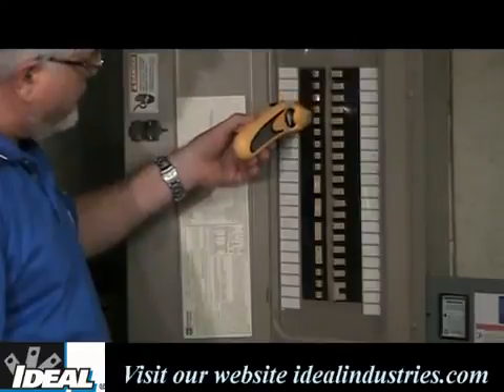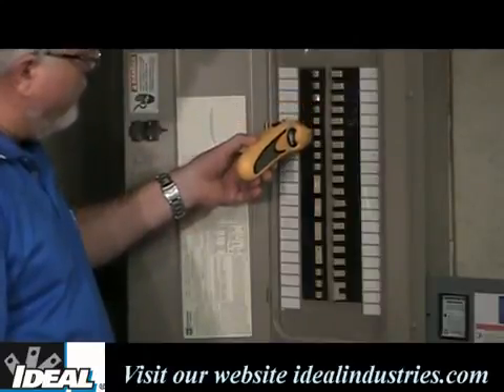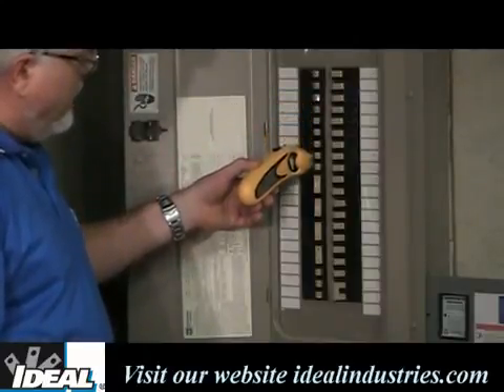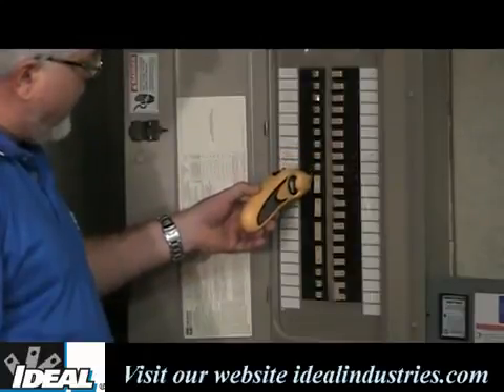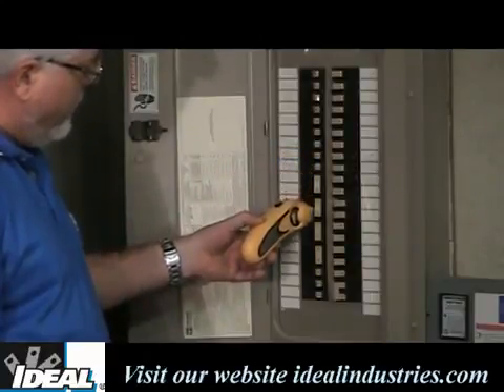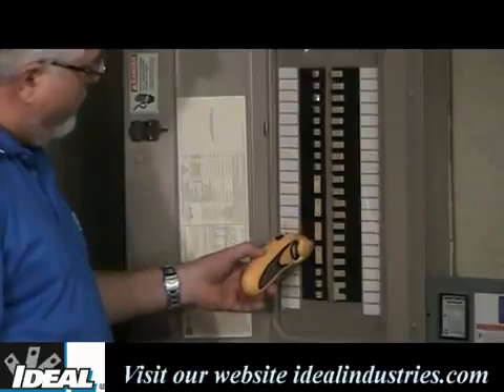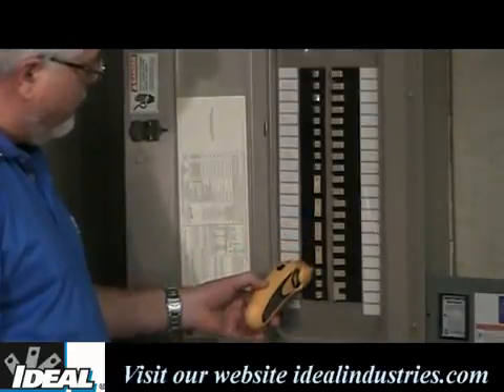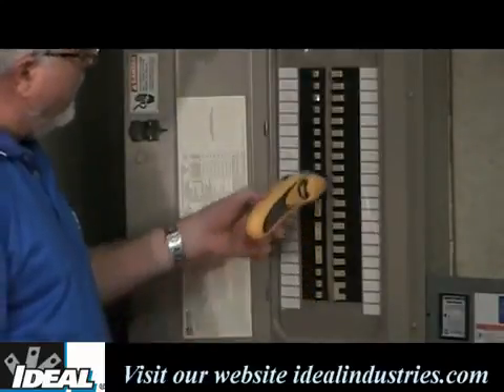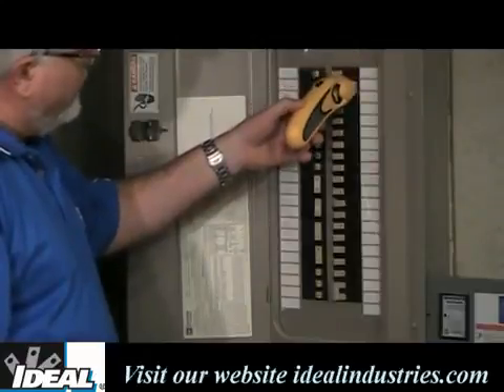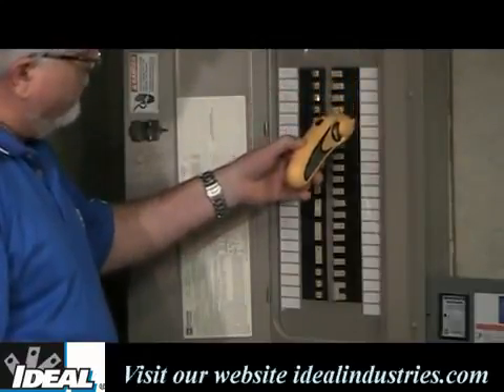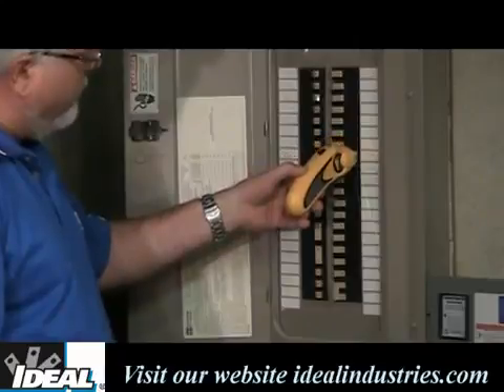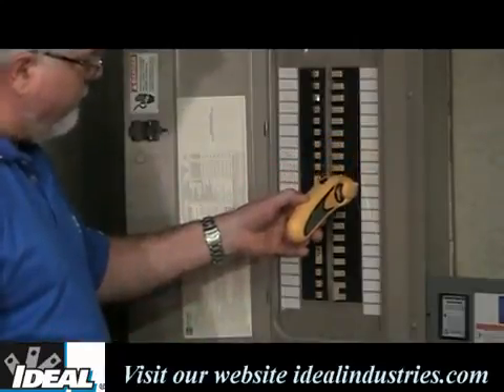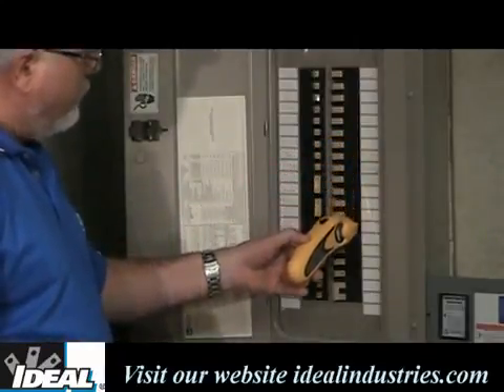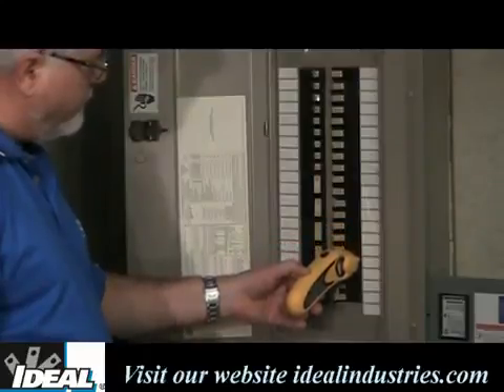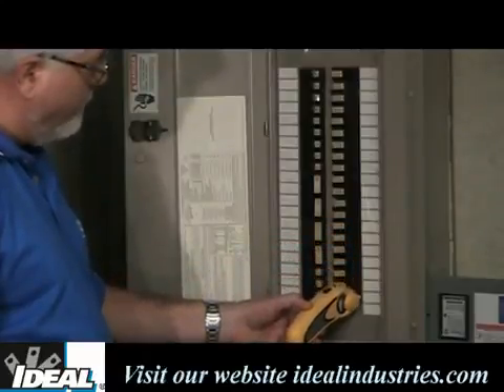I'm going to slowly go through the panel, giving just a half second on each breaker, running it through the entire panel. You can see it's beeping on several of these. Just give it that little half second as you slowly go through, staying flush on the front face of all the breakers. We go through the panel one time like this. There was one final one.